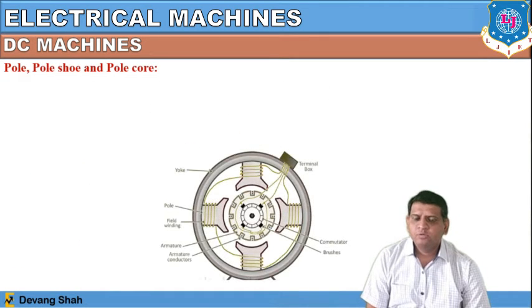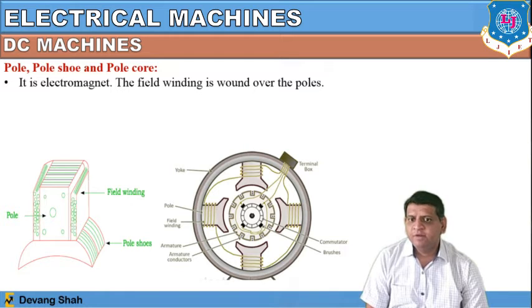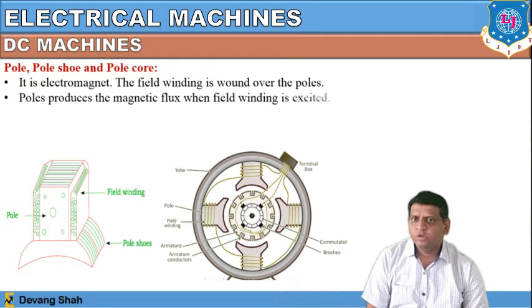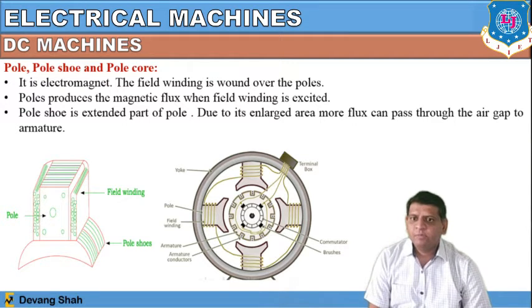The next parts are the pole, pole shoe, and pole core. This portion is defined as the pole, this is the pole shoe, and the overall portion is the pole core. It is an electromagnet. The field winding is wound over the poles, and the poles produce magnetic flux when the field winding is excited. The pole shoe is the extended part of the pole — due to the enlarged area, more flux can pass through the air gap to the armature. It is made up of cast iron and silicon steel.